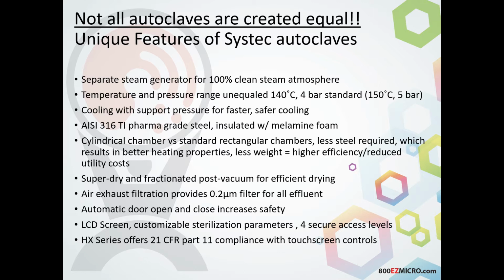We offer cooling with support pressure for faster and safer cooling. What that allows us to do is run cooling coils inside of the system and then pressurize the vessel as well with sterile compressed air. That will allow us to cool down and completely keep all of your liquids intact. So no longer do you have to put 1 liter of media in a 2 liter bottle to get your media back. With our cooling system, we are able to put 1 liter into a 1 liter bottle, and you're going to have less than 3% liquid loss during that cycle.